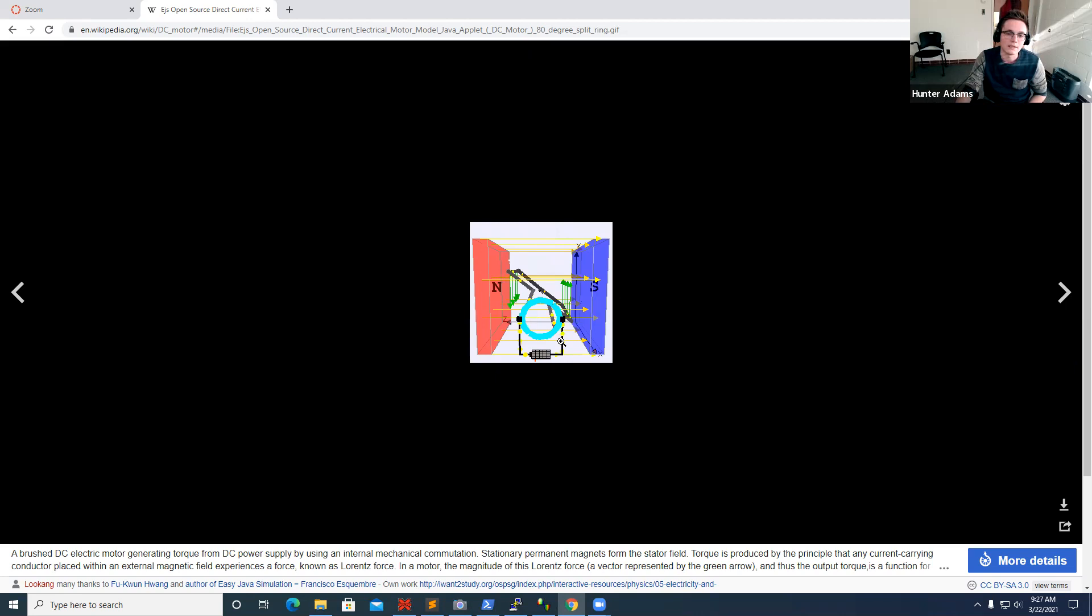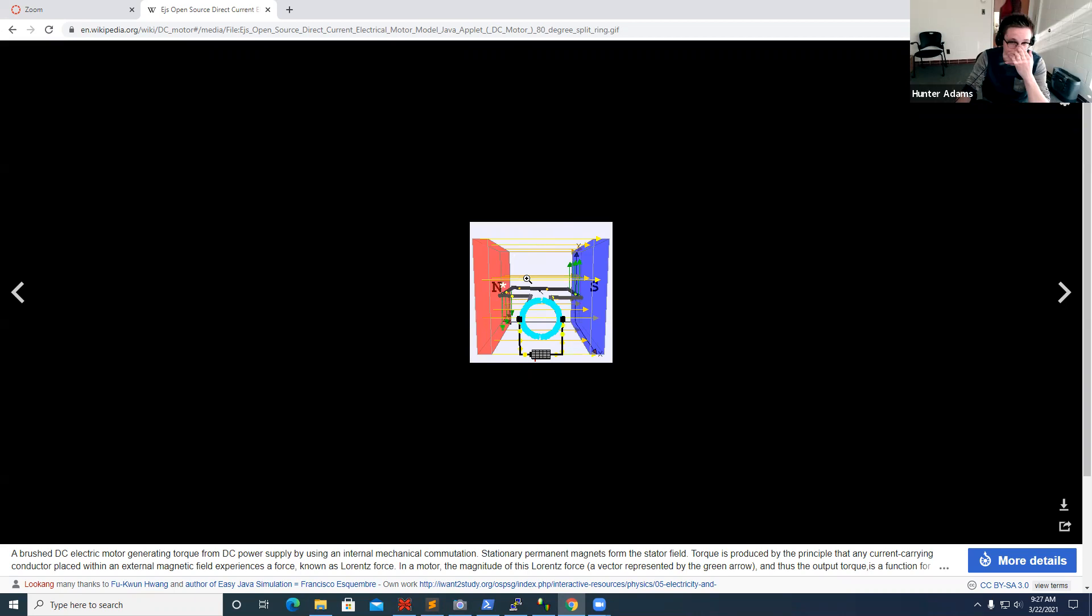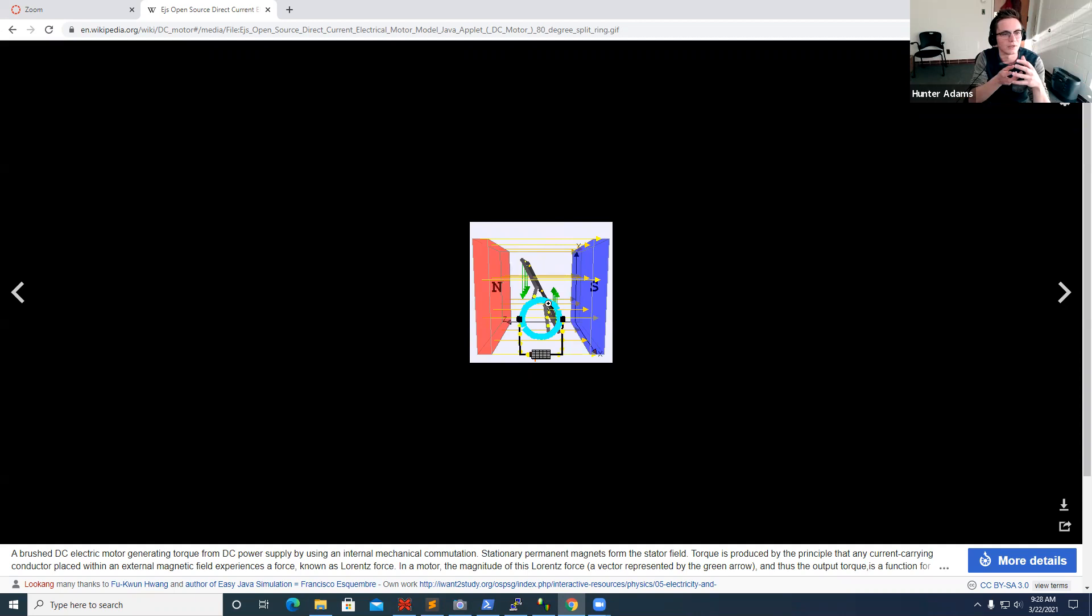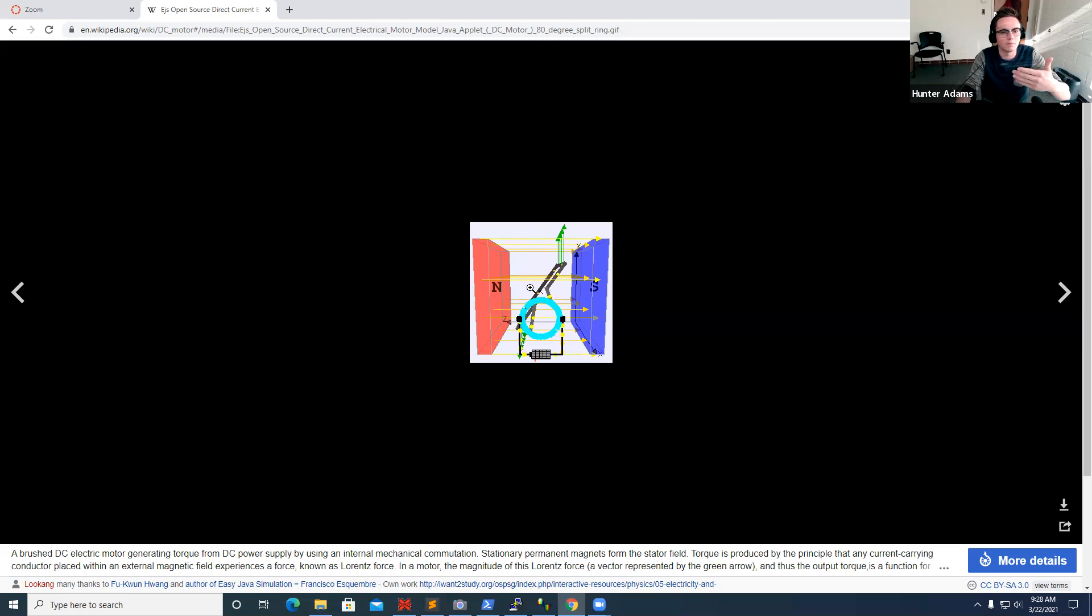What you're seeing in the foreground of this circular piece is called the commutator. This solves a tricky problem, which is, for this particular construction of a DC motor, the way that we are making the motor work is by putting current directly into the armature. The armature spins, right? So clearly you can't just use wires to connect to the outside world because they would very rapidly twist themselves up. So what this does is it is essentially a ring-shaped brush where all of the brush fibers are conductive elements. It is spring-pressed against this armature so that the armature can spin on top of this brush mechanism and is free to rotate, but electrical contact is maintained.